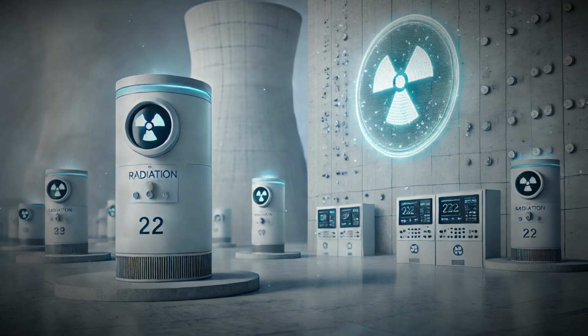There are several types of radiation relevant in a nuclear facility, including alpha particles, beta particles, gamma rays, and neutrons. Alpha and beta particles can be blocked by relatively thin materials, but gamma rays and neutrons are highly penetrating and require dense shielding, such as thick concrete walls or heavy metal barriers. Inside the reactor building, radiation levels are highest near the core, so shielding structures such as the biological shield and the containment walls are designed to absorb and reduce radiation to safe levels.